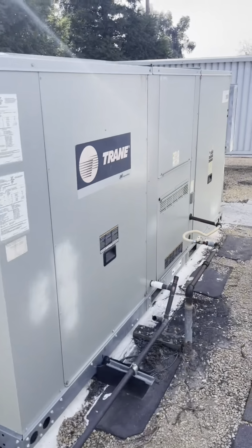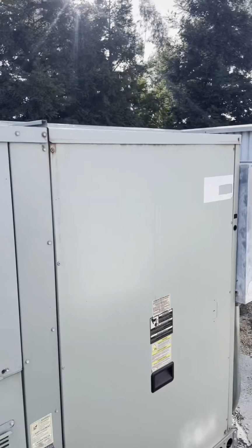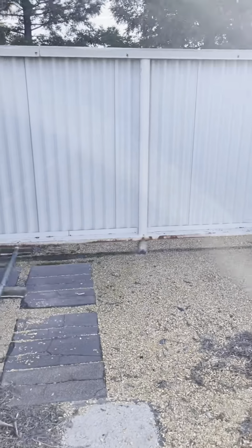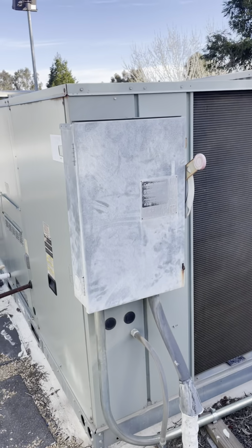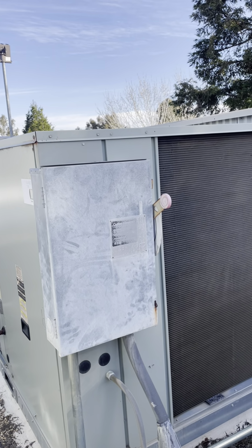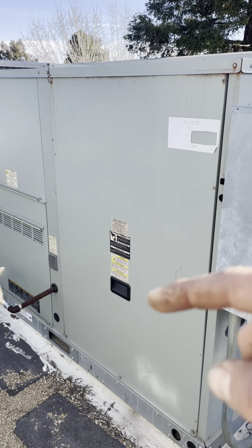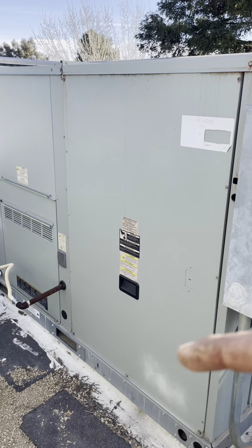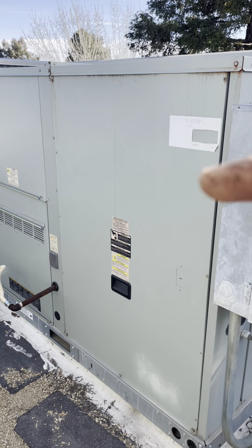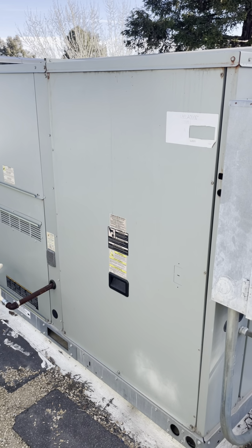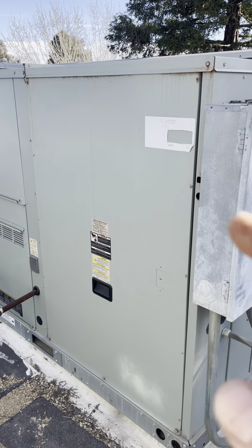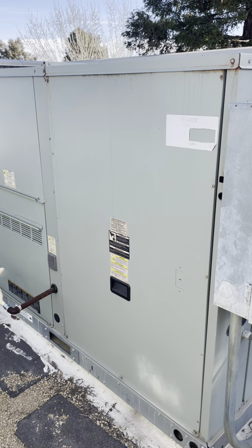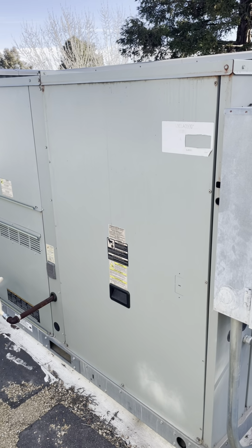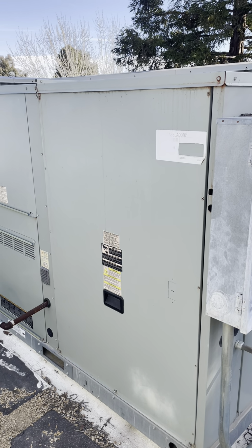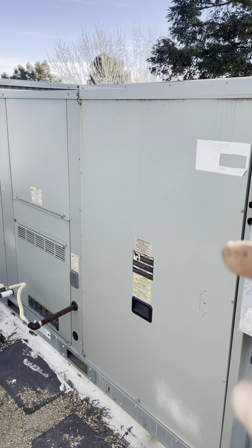So this site has an interesting ductwork system where this unit and that split system we're working on share ductwork. And there's a backdraft damper that prevents the units from blowing back into each other. Since the system is set up this way, sharing the ductwork, we don't want this fan running if that unit's the one running. Okay, it just shut down. I'm gonna go ahead and double check that as well to make sure that we're not blowing both fans at the same time, because that would cause an issue. I think if both fans run at the same time, our split system freezes over.